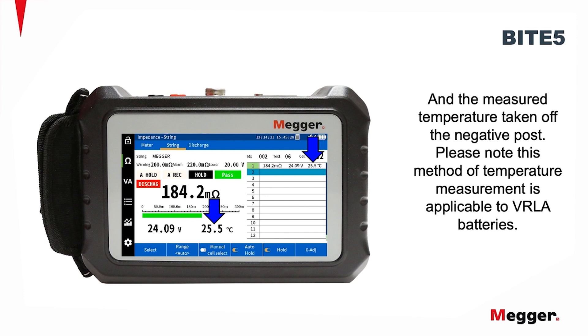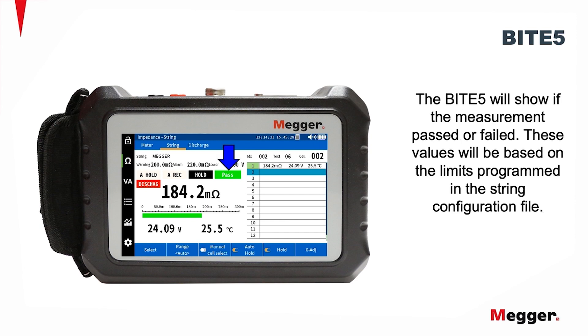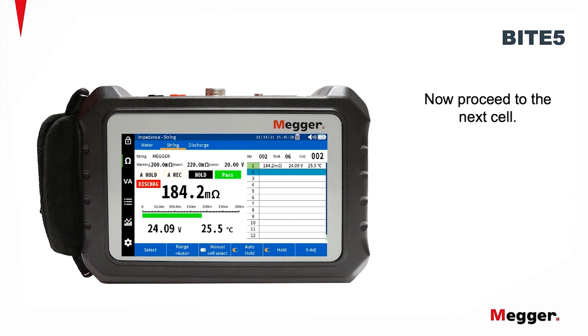Please note this method of temperature measurement is applicable to VRLA batteries. The BITE5 will show if the measurement passed or failed. These values will be based on the limits programmed in the string configuration file. Now, proceed to the next cell.